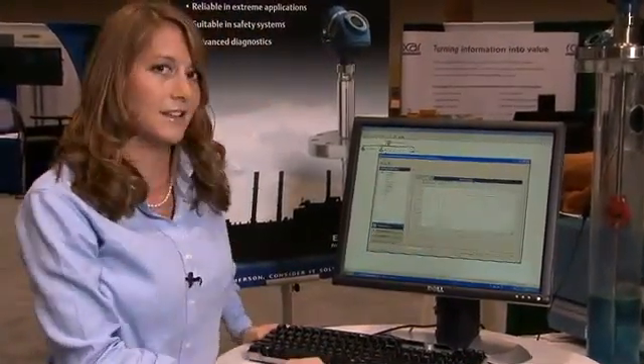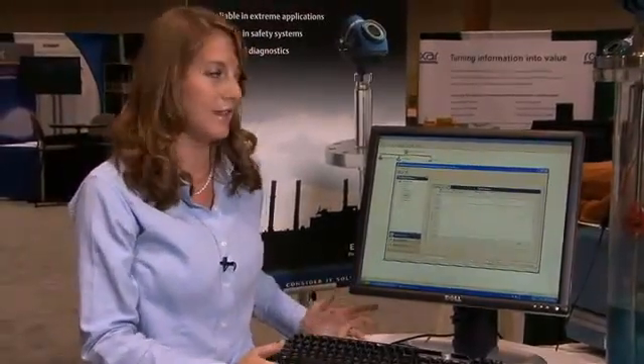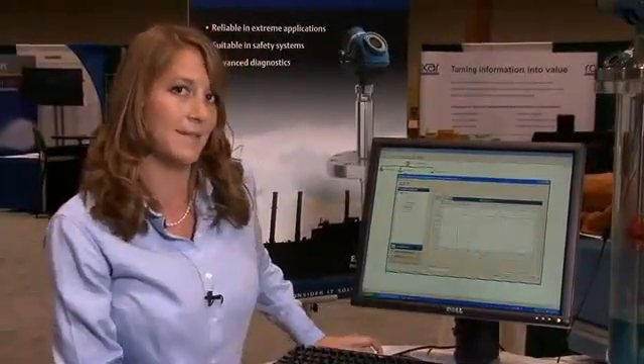The advantage of the intelligent diagnostics is that it can give you an idea of how clean or how reliable the installation is. In this situation we have a slight disturbance here caused by some contamination.